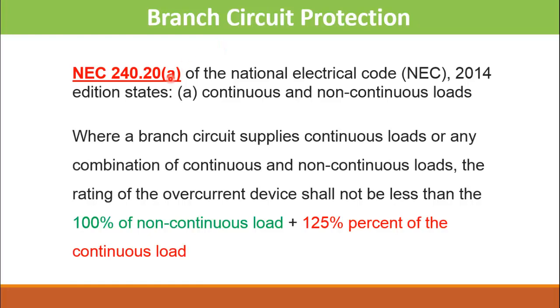The NEC standard that defines branch circuit protection is NEC 240.20(a), which states that where a branch circuit supplies continuous loads or any combination of continuous and non-continuous loads, the rating of the overcurrent device — which can be a circuit breaker or fuse — shall not be less than 100% of the non-continuous load plus 125% of the continuous load.